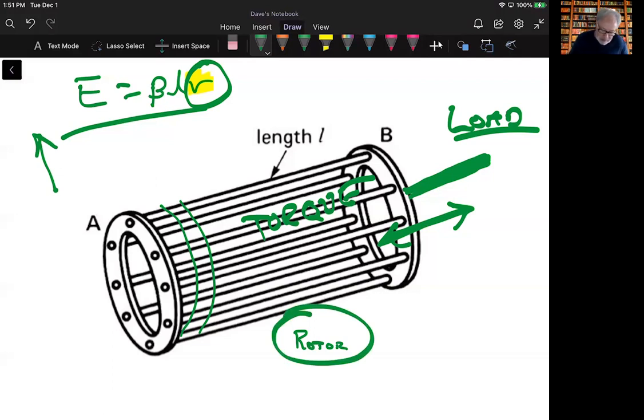Under normal loads, induction motors run very close to the speed of the magnetic field, to the synchronous speed. Thus at full load, the slip for a large motor - we're talking very large, 1000 kilowatt motor - is about 0.5% of synchronous speed.